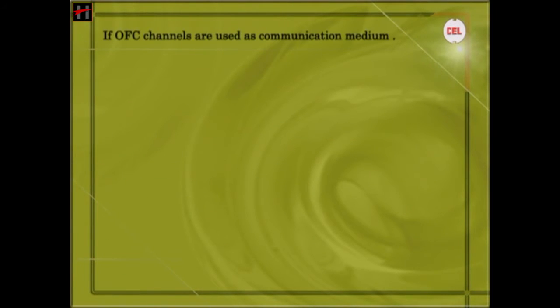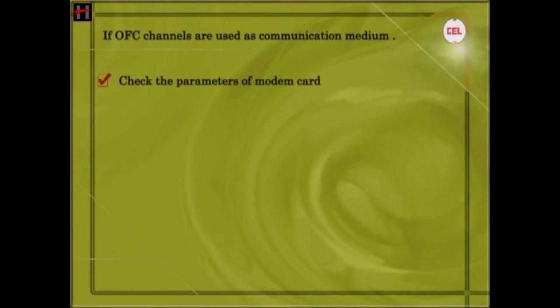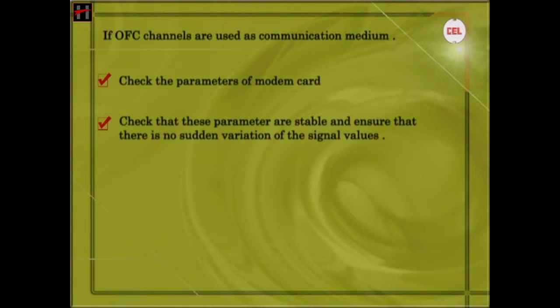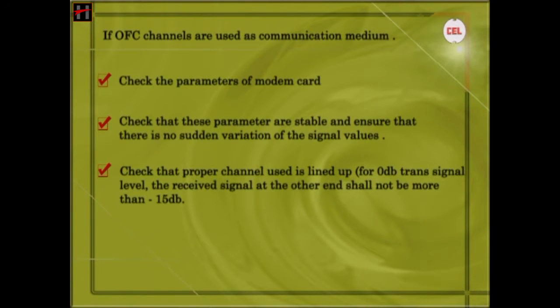In case OFC channels are used as communication medium: 1. Check the parameters of the modem card. 2. Check that these parameters are stable and ensure that there is no sudden variation in the signal values. 3. Check and ensure that the proper channels used are lined up as specified in the checklist.